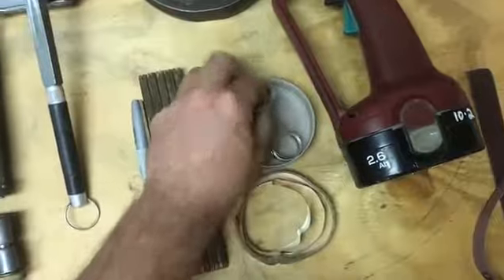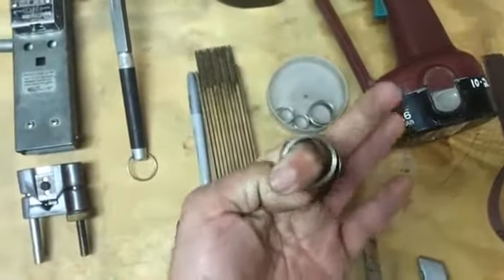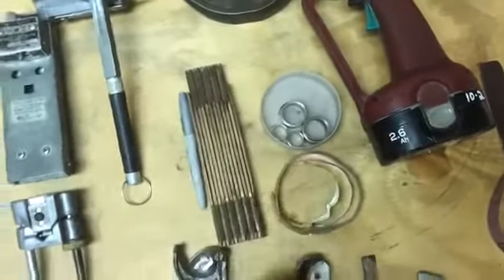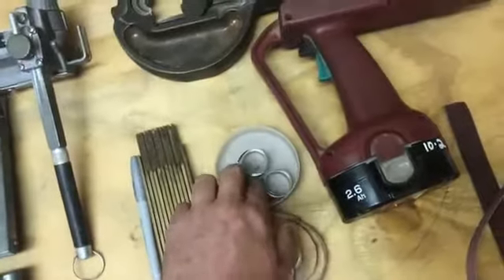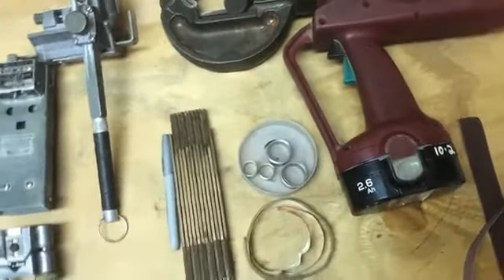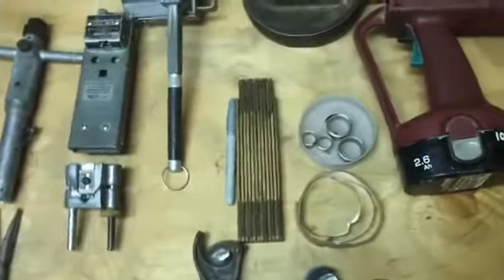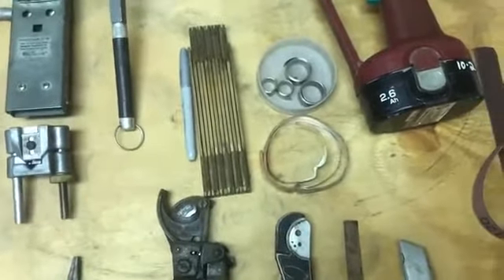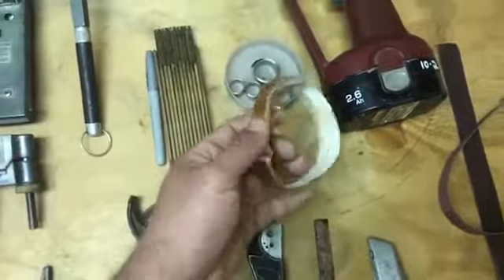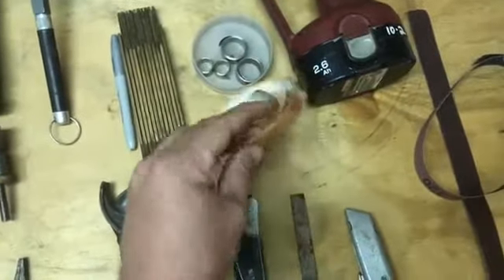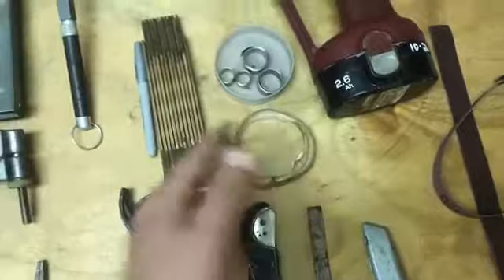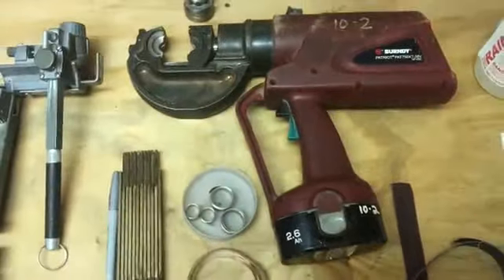These are constant force springs. This is actually a steel spring that has memory to it, just like the wristbands I used to get as a kid. And these come standard in ground kits, just like that. And just throughout the years, just any extra parts and pieces, these are really handy for doing cutbacks on cables. So if you run into those, I'd recommend just holding on to a couple. They'll come in handy, and I'll show you why. This is copper tape, and this comes in handy for doing a cutback on the tape shield cable, which we're using. So I'll show you what that's for here in a little bit.